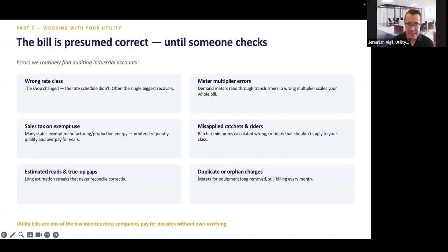Here are six things we often find, and we're giving this to you for free. Number one is the wrong rate class. Often your shop has changed—you've added or removed equipment—and the utility vendor doesn't know that. They don't know what's in your building or what kind of pull your operations require each day. That's the biggest way to recover funds: finding out you're on the wrong rate class because no one's changed it in years.